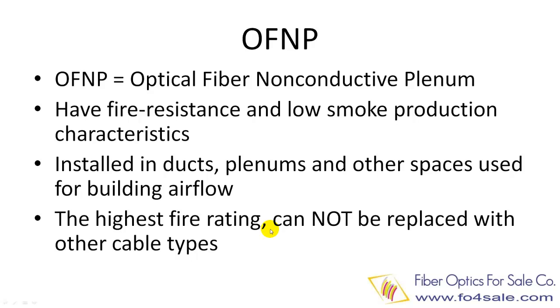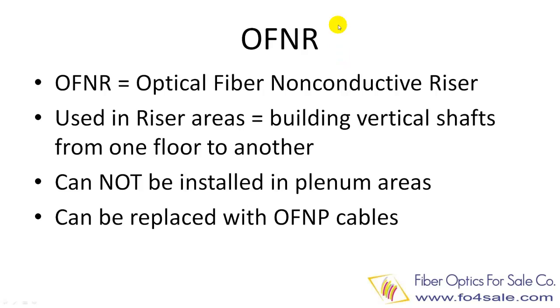OFNP cables are the only type of cables that can be installed in the plenum area for HVAC air return. This is the highest fire rating cable — no other types can be used as a substitute for OFNP cables. The second type of fiber cable rating is called OFNR. N still stands for non-conductive, and R stands for riser rated. OFNR cables are used for riser areas, such as vertical shafts or runs from one floor to another. OFNR cables cannot be installed in plenum areas, but OFNP plenum rated cables can be used as a substitute for OFNR cables.